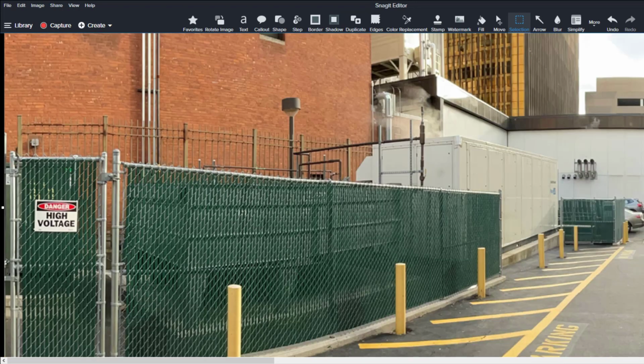It's a true combined heat and power technology, which means that when you're making the power, you're also able to harvest the waste heat and use that for the domestic hot water. For an apartment building, you have a year-round need for domestic hot water for the showers and whatnot. So we're able to get basically twice as much benefit from the same amount of natural gas as you would if you were just burning natural gas for a boiler, whether it's to heat the building or heat the domestic hot water. The fuel cell is actually a hydrogen fuel cell, and it reforms natural gas into hydrogen before it is used by the fuel cell.